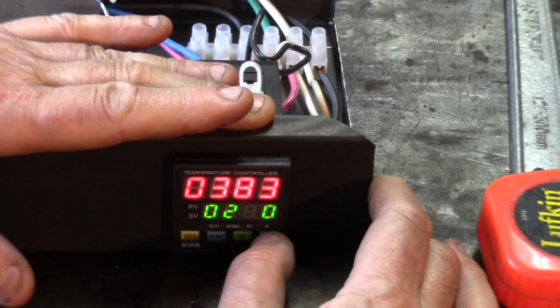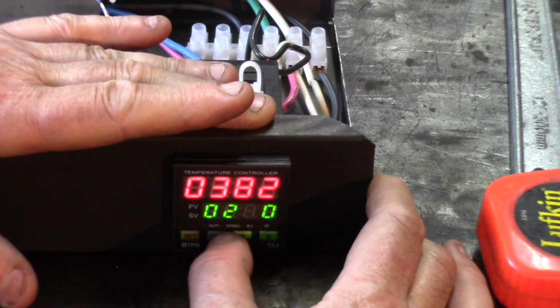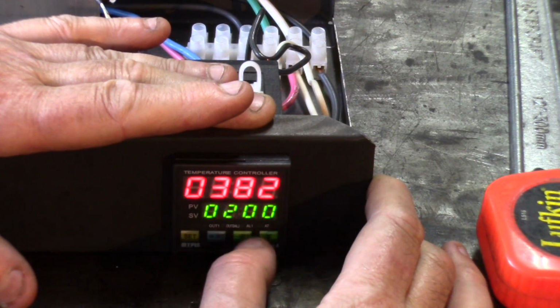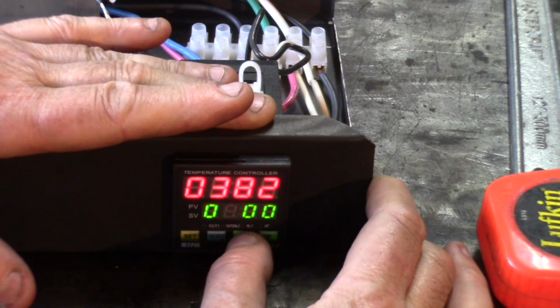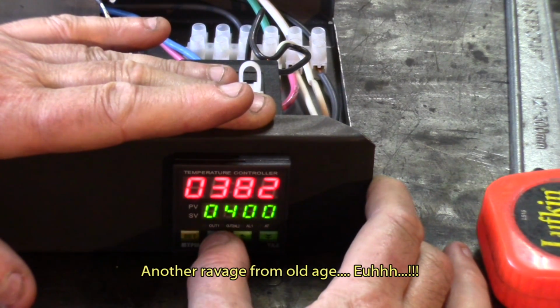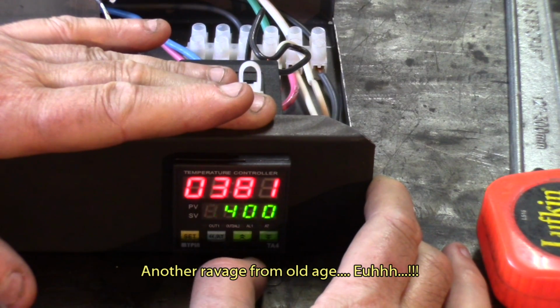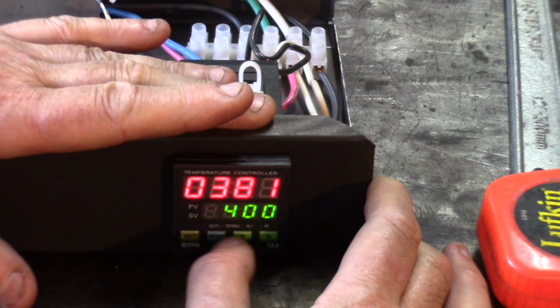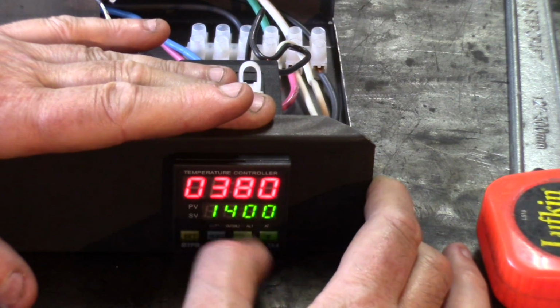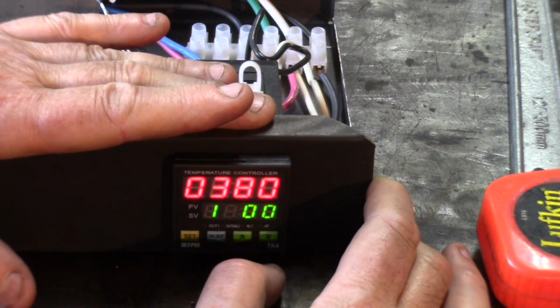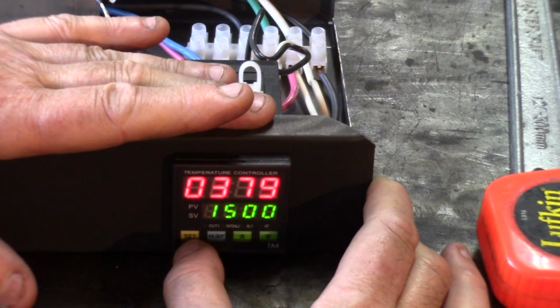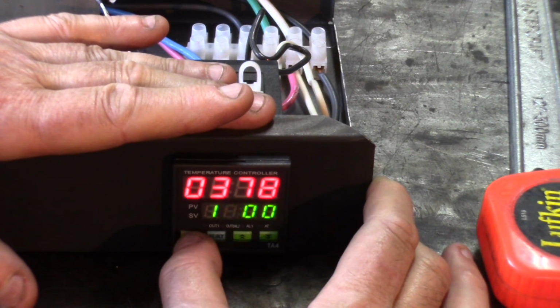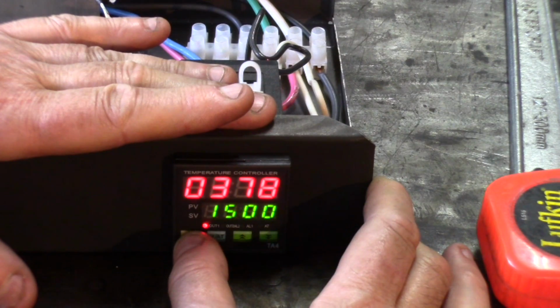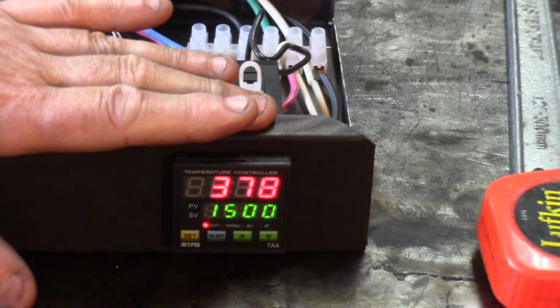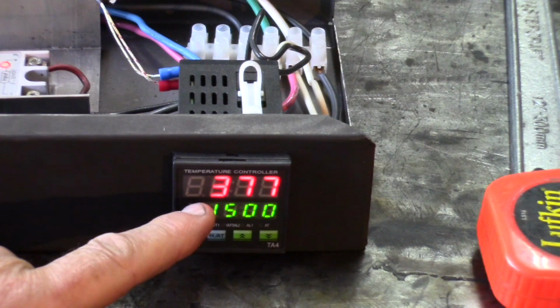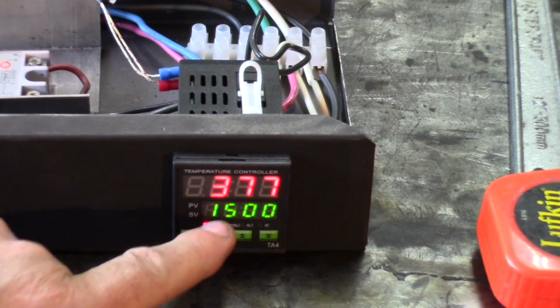I need to put a 0 there, a switch column. I need a 4, and I need there a 1. Let's see. Oh sorry, I need a 5 there. So, 1500 degrees, it's easy. Once I'm happy with the settings there, which is going to be my final temperature, press set, and it's going to go from the temperature it is now to 1500 degrees.